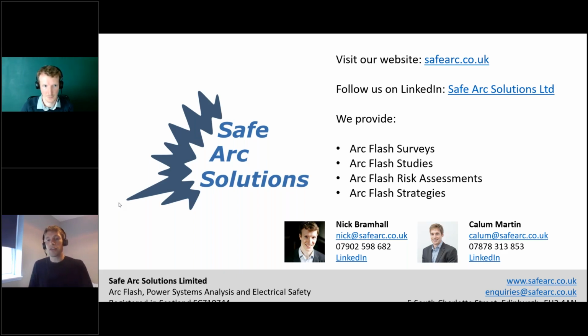In terms of arc flash, we tend to fall in line with the NFPA 70E guidelines, which are to revisit your arc flash study every 5 years to see what could have changed on your site. But also if you have any significant changes, for example, if you replace a switchboard, or introduce or remove any generation or sources of short circuit fault current, then that is a good time to rerun your arc flash calculations to see if there have been any significant changes to your risks.